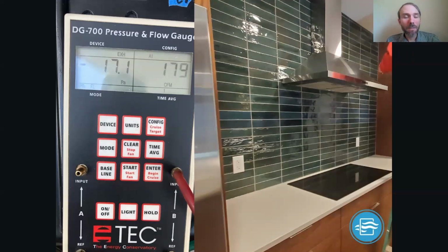If this system is not ducted, as many are not, and it's just recirculating, this may require a whole kitchen makeover to place the stove in a location that will allow the kitchen to be vented. Then you will ensure proper flashing and sealing of the vent penetration. The qualified energy rater should test the system to see if you need an updated one. If the system tests over 400 CFM, this would cause a different problem that you need to address, where you need to bring in makeup air to prevent negative pressure in the house. Kitchen ventilation could also instead be taken care of with an energy recovery ventilator that's being supplied through your existing ductwork, like we talked about, as long as it hits 5 air changes per hour within that kitchen space.